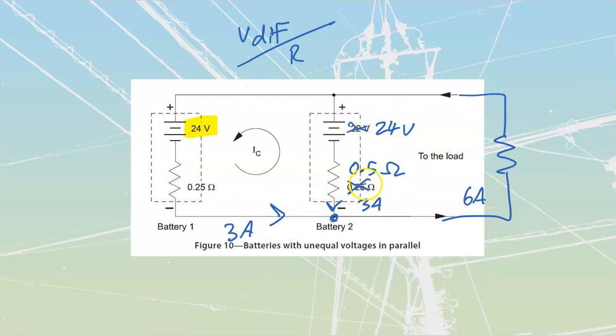It's not going to work out quite like this. Take a look at this: 24 volts, 0.5 of an ohm. V equals I times R. So if I take 3 amps traveling through 0.5 of an ohm, that gives me a voltage drop of 1.5 volts before I even leave this transformer winding. It's the DC equivalent that we're drawing here.